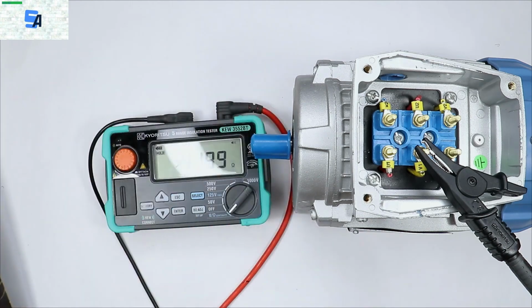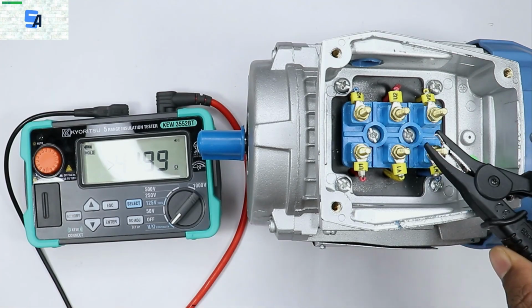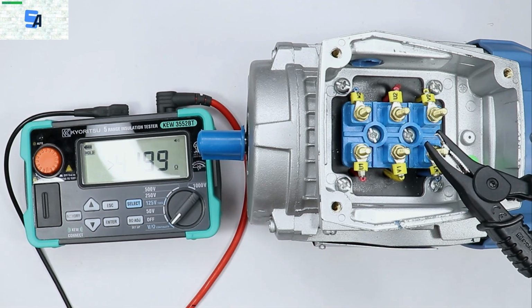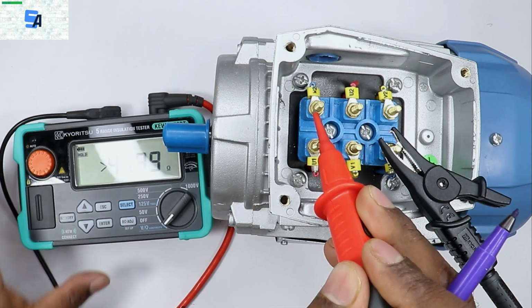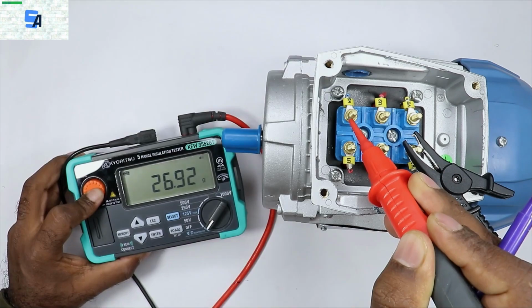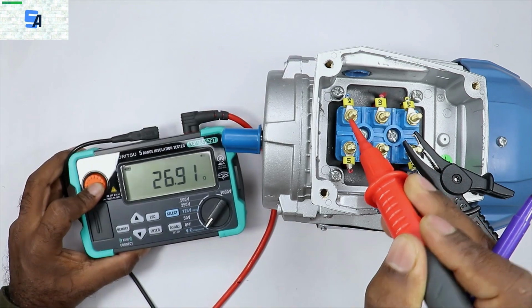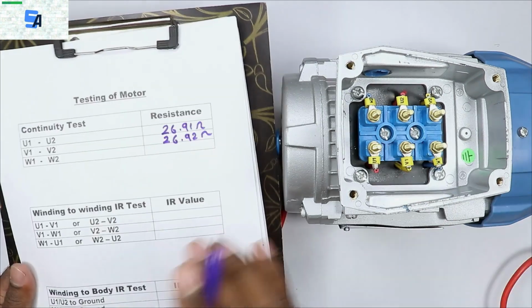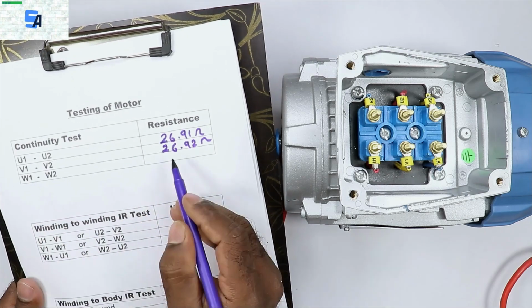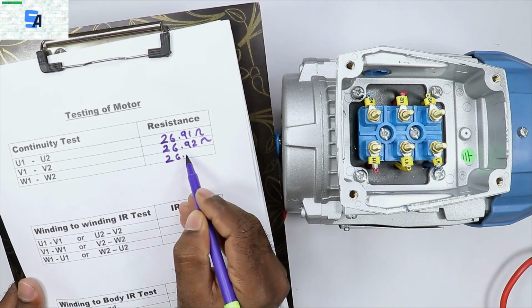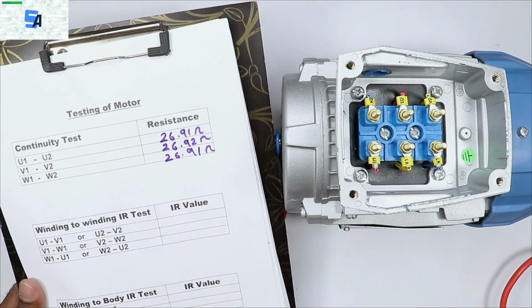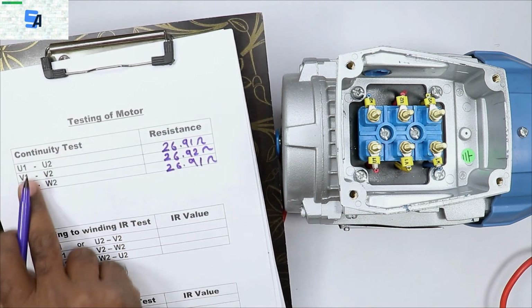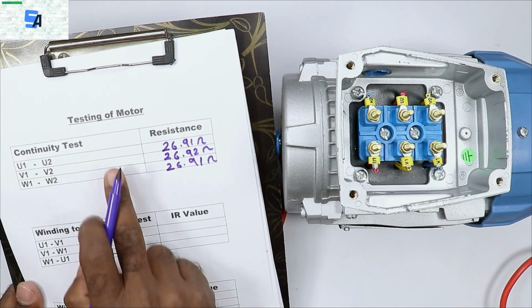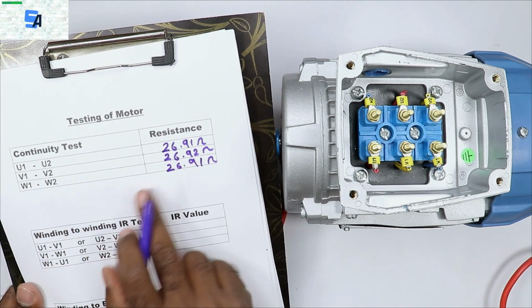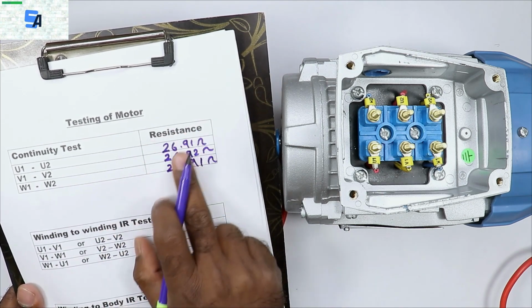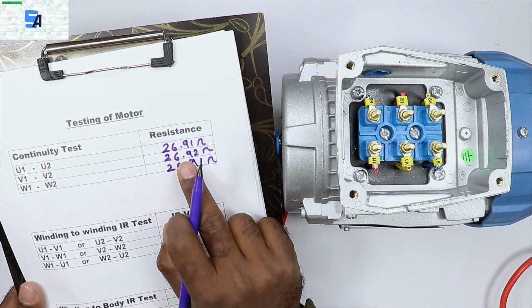After this, the third winding here, we will measure the resistance of this winding also. So I am measuring the resistance of the third winding here. On measuring, we are getting a value of 26.91 ohm. It means here also the resistance value is the same. This third winding, W1, W2, its value is also 26.91 ohm. As you can see, in this continuity test, for all the 3 windings, we are getting the same resistance value. There is a difference of 0.01 ohm, but it is almost the same.